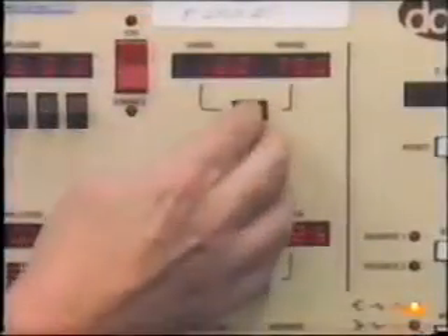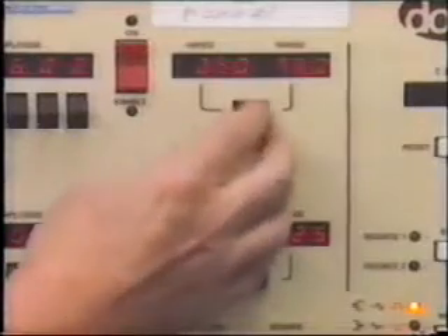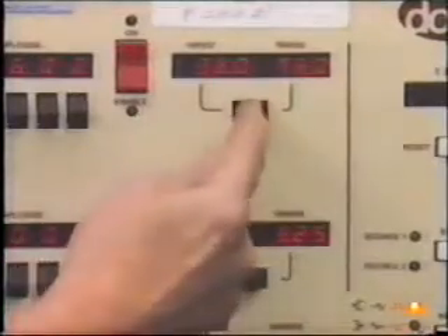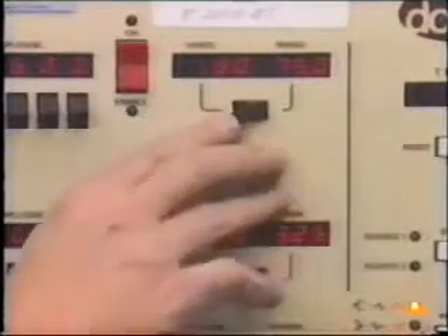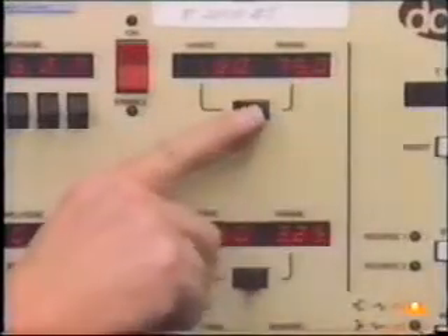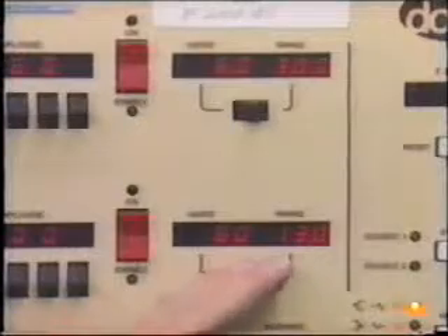Test signals can be produced over a wide range of frequencies. Pressing this flipper switch to the left changes the source's frequency from 60 Hertz all the way up to 600 Hertz in multiples of 60 Hertz. Pressing it to the right changes its source's range: 75, 150, 300 volts AC, or 3.25, 13, 26 amps AC.